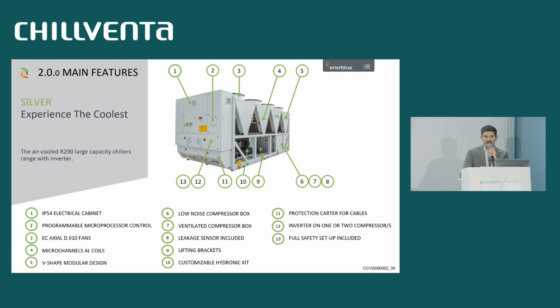The electric panel is IP54. The controller of the unit is a programmable one. We wrote the software at our facility. And the fans, of course, are a standard for monoblock chillers. So EC fans, axial fans of 910 millimeters from a German supplier. The unit is equipped with microchannel coils, which are a standard for chillers nowadays, in V-shape form.